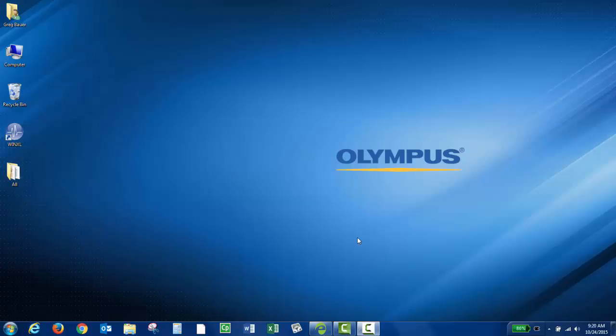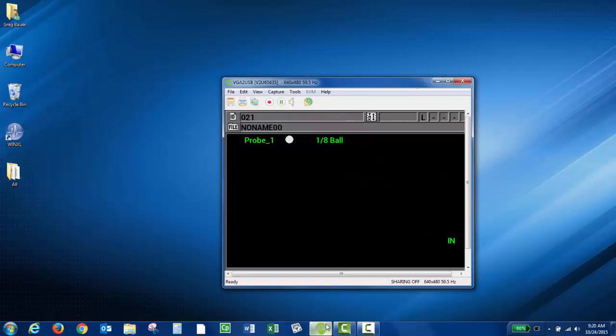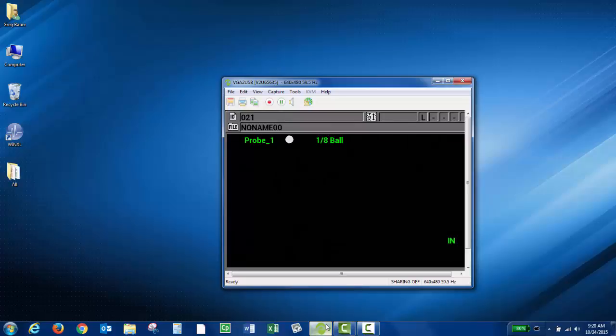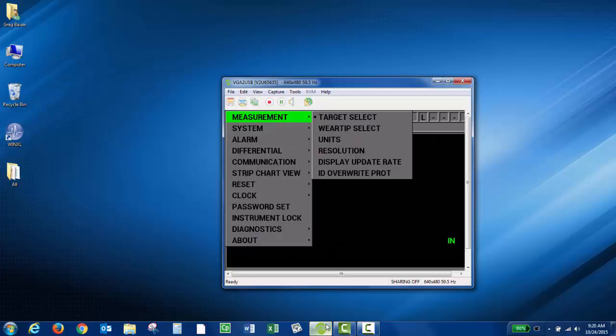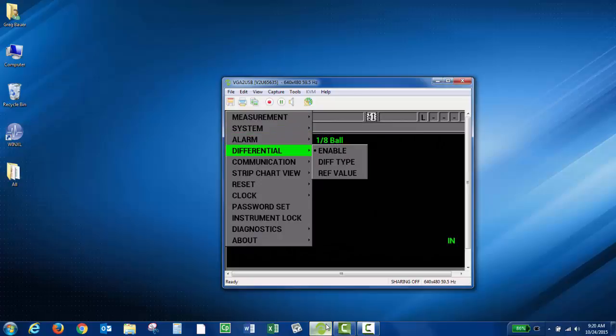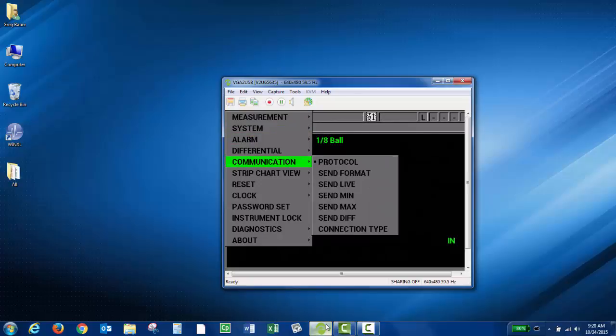So the first thing you want to do is check the communication settings on your instrument. I'm using a VGA to USB adapter so you can see the screen of my unit. Go ahead and press setup on the instrument, then press the down arrow to communication and press enter.